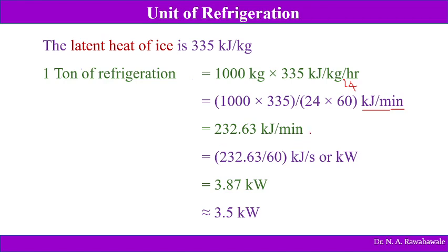Converting 232.63 kilojoules per minute to kilojoules per second (kilowatt) by dividing by 60, this works out to be 3.87 kilowatt. Approximately it is taken as 3.5 kilowatt — so one ton of refrigeration is taken as 3.5 kilowatt, or it is sometimes expressed as 210 kilojoules per minute, as found in books.